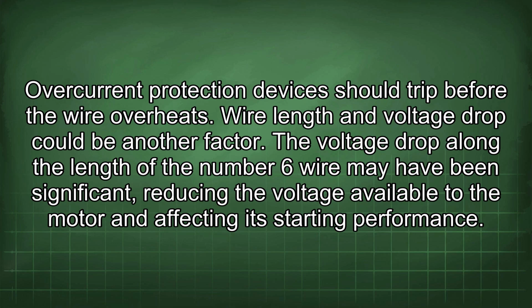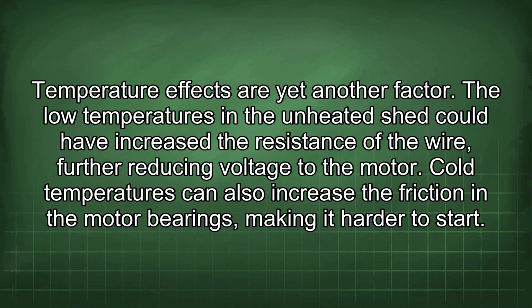The voltage drop along the length of the number 6 wire may have been significant, reducing the voltage available to the motor and affecting its starting performance. Temperature effects are yet another factor. The low temperatures in the unheated shed could have increased the resistance of the wire, further reducing voltage to the motor. Cold temperatures can also increase the friction in the motor bearings, making it harder to start.